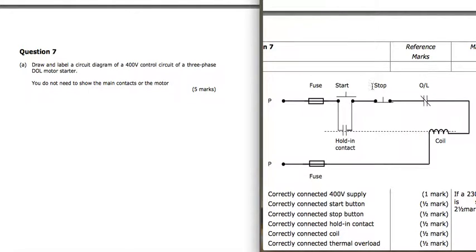So when we press the start, the coil energizes, the motor comes on, it operates this contact as well, and so when we take our finger off this button, we still get the supply through the holding contact, and we can stop the motor by pressing this stop button, which de-energizes the coil and de-energizes the holding contact.